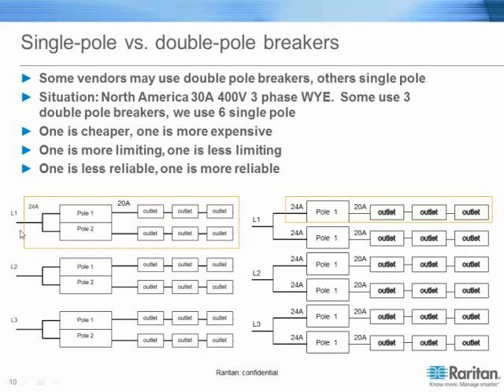If we look at this, we have our line coming in here. These 6 outlets are covered by only one 20 amp breaker. It's very easy with 6 plugs - think about some of these draws on these servers, we're seeing Cisco switches out there with 500-600 watt power supplies. If you don't know what you have in that PDU and you start plugging stuff in, you're going to trip that breaker.